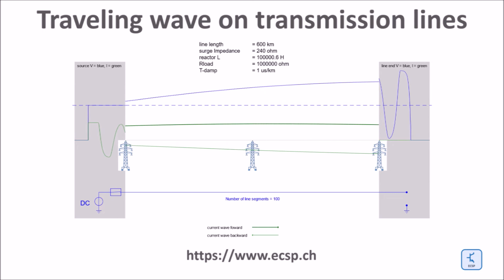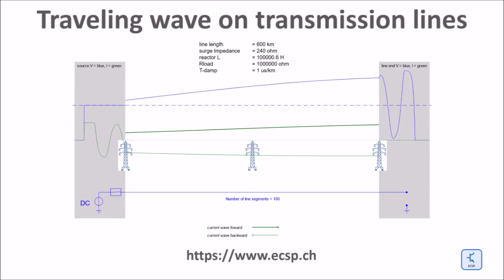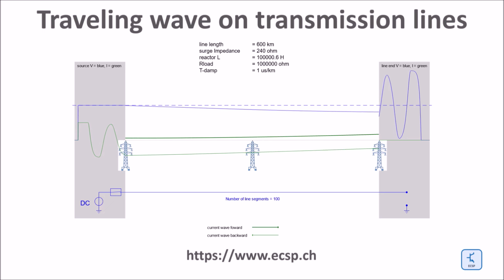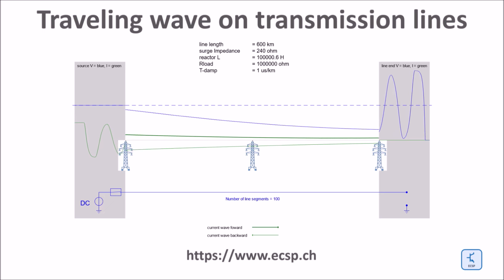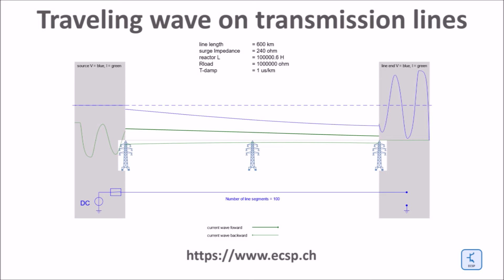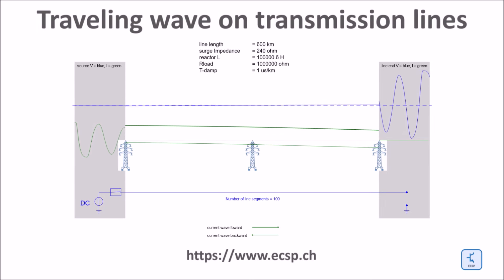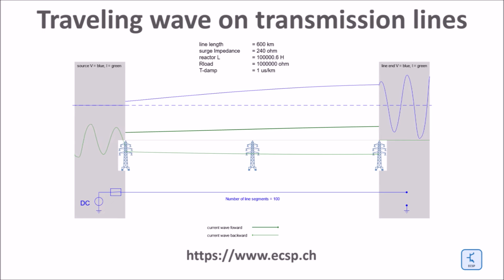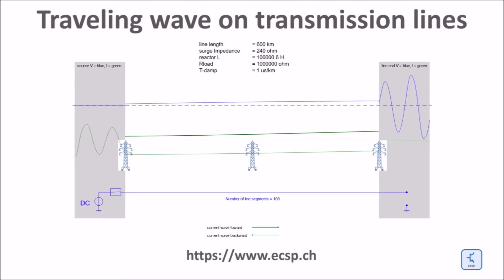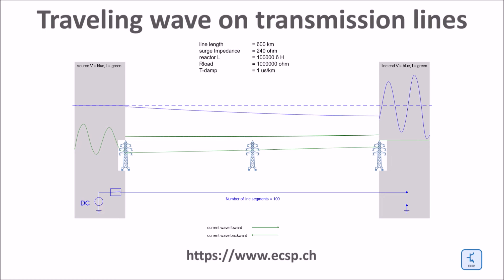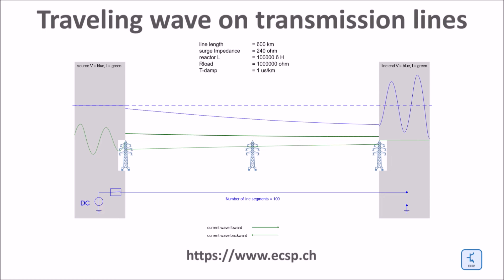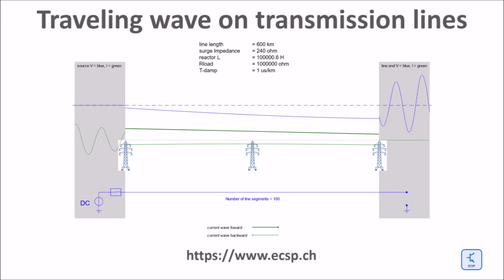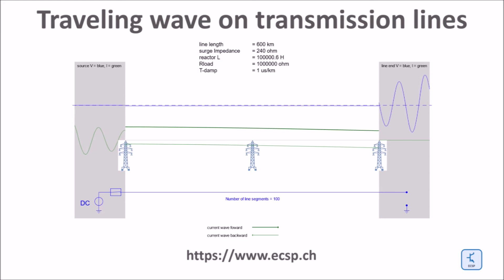On a real line the damping would happen along the line, but there is no relevant change for the voltage and current curves on both line ends. The result can be seen at the voltage curve on the line ends to the right side, where the square wave is gradually transformed into a sinusoidal oscillation given the damping of the high frequency spectrum. Such a voltage shape is more realistic for such a long line compared to the theoretical square wave shown before.